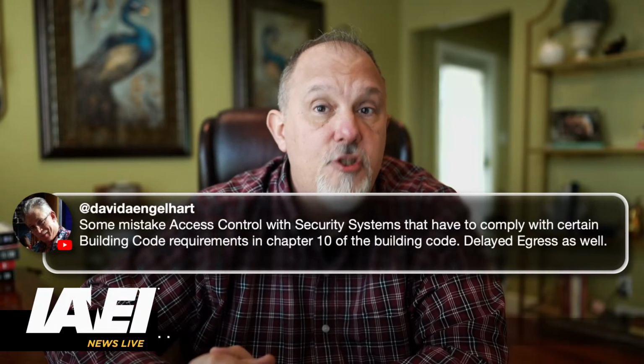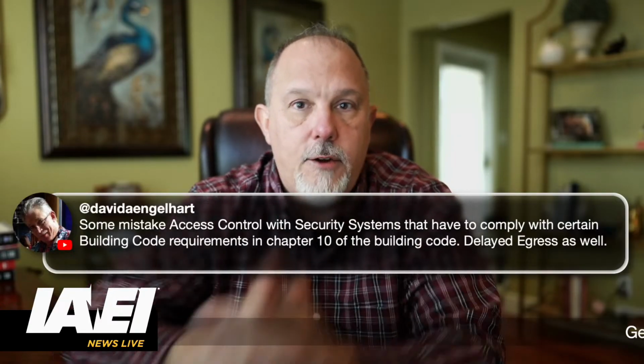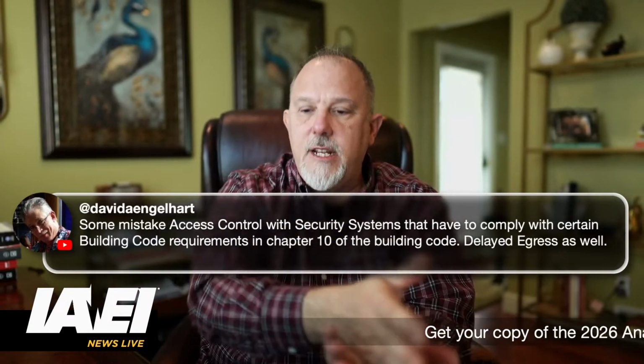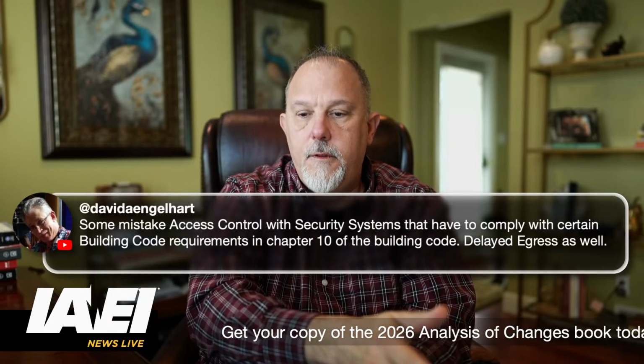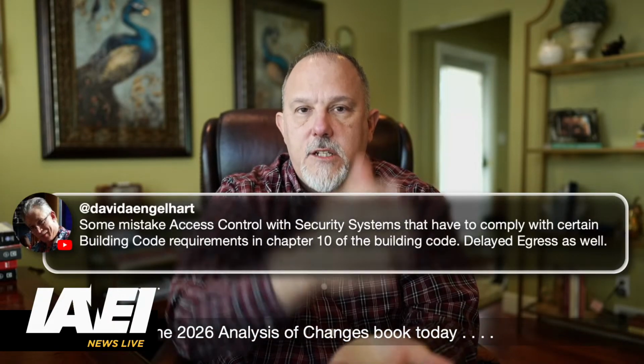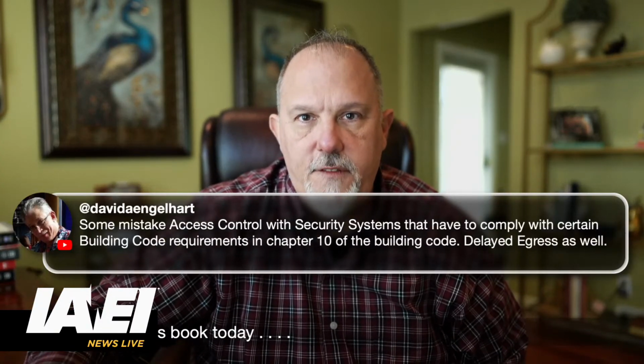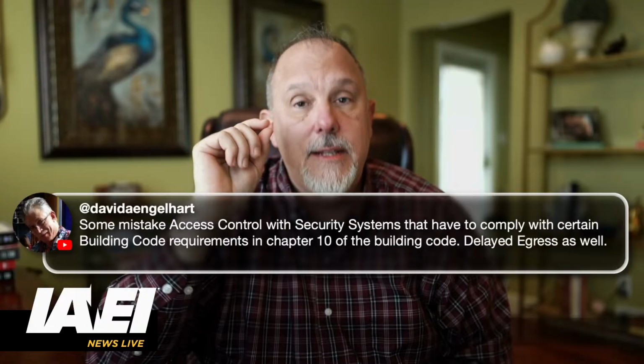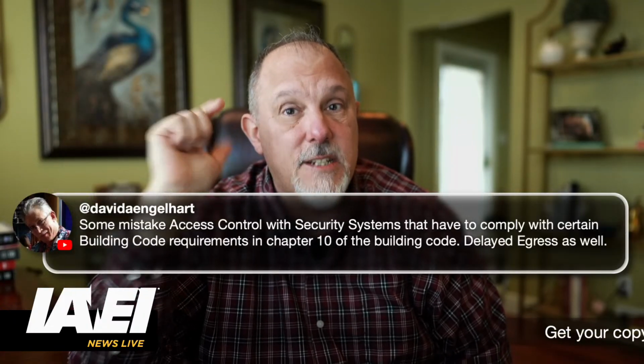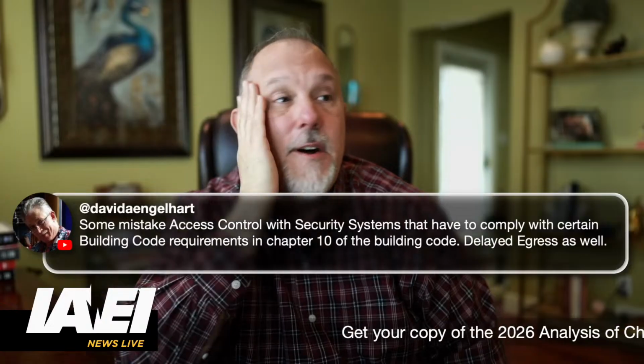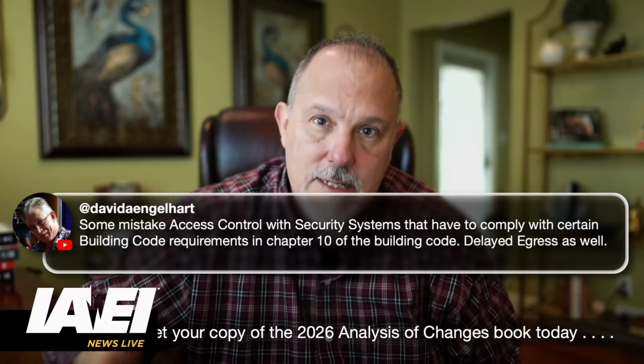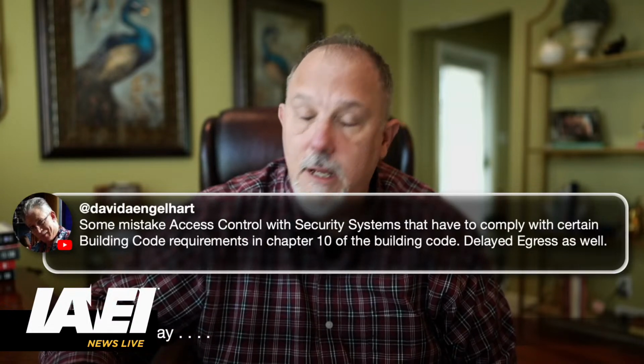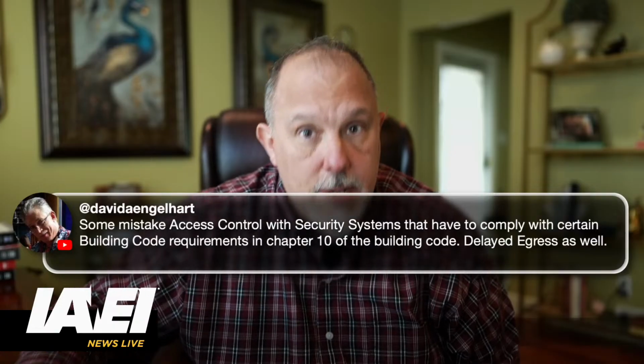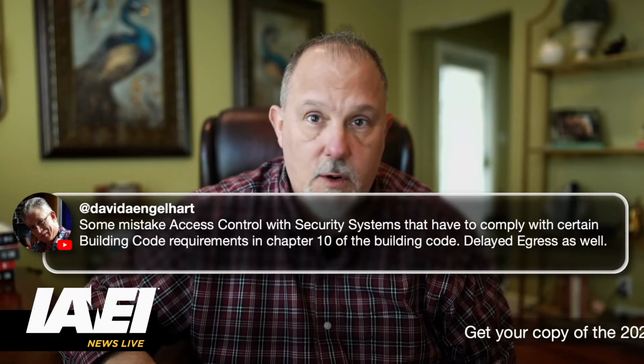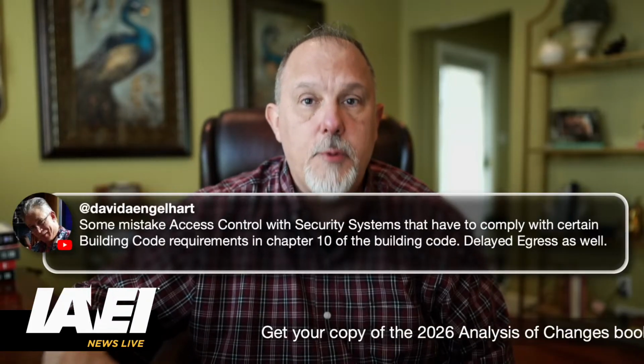Now, you and I both know if I say solid state transformer, you're going to want to go to Article 450. Well, that's not the case, because it's listed to a standard that addresses solid state power supplies. On that call, I made the statement: look, we're calling it a solid state transformer, but we need to call it what it is and how it's listed, which is a medium voltage solid state power supply. It's not a transformer. If I say transformer, it brings in implications.